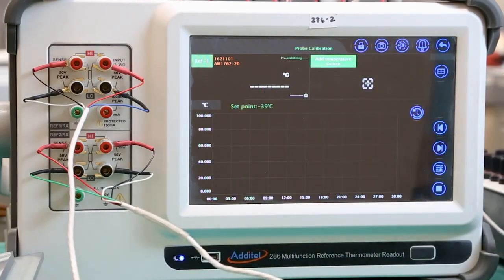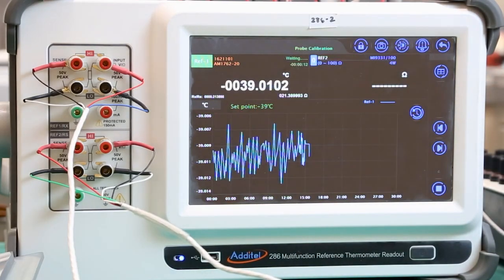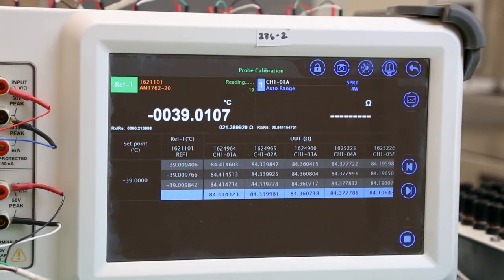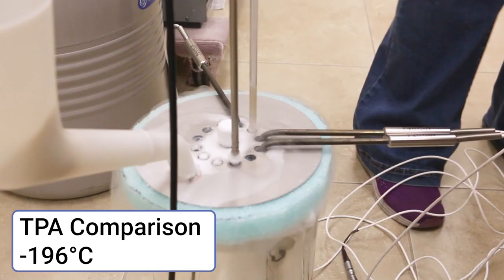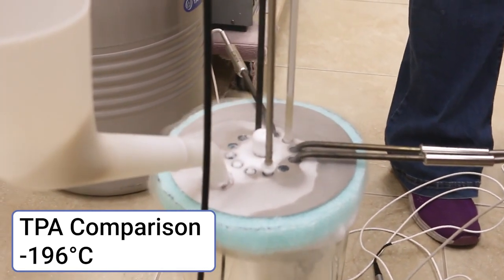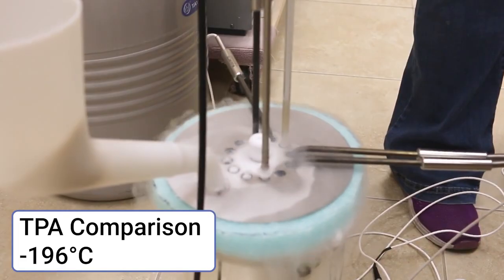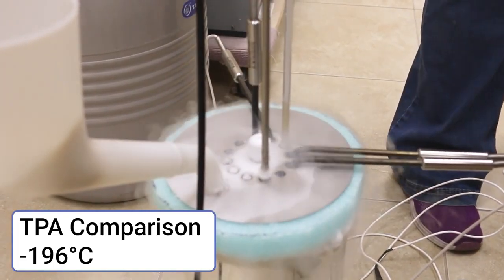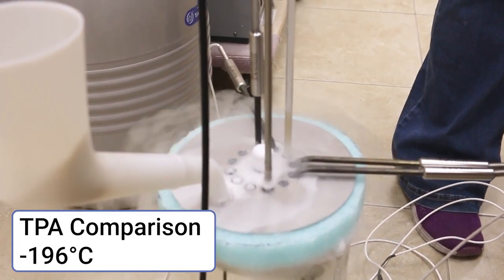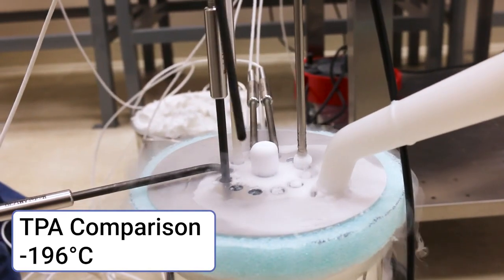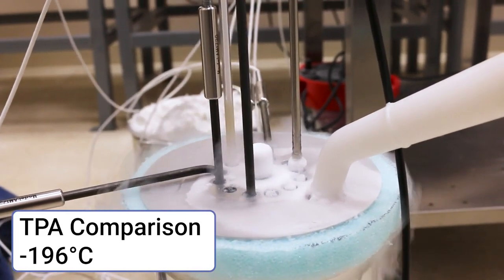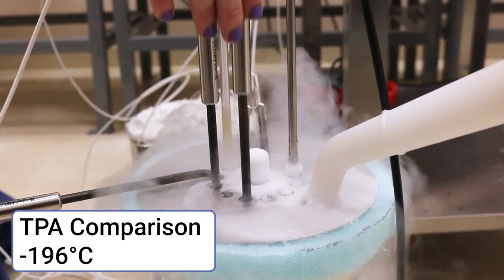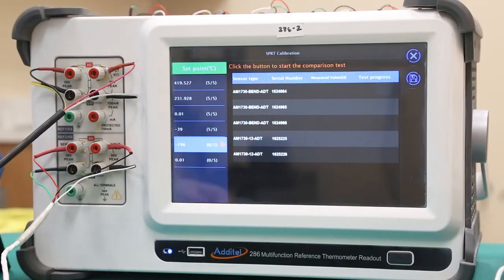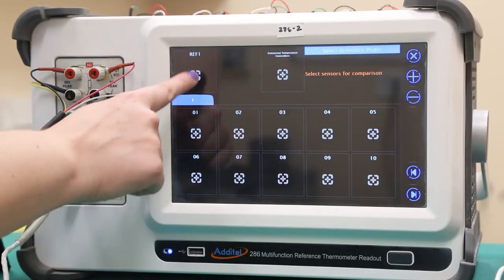This portion of the test is fully automated and will end with a pop-up window once all probes have been measured according to the test settings. The next calibration point, the triple point of argon, will also be done using a comparison test by using a liquid nitrogen comparison calibrator at the temperature of roughly -196 degrees Celsius. Once the DUT probes and a reference probe have all been inserted into the liquid nitrogen, the same procedure as the previous comparison test should be followed.